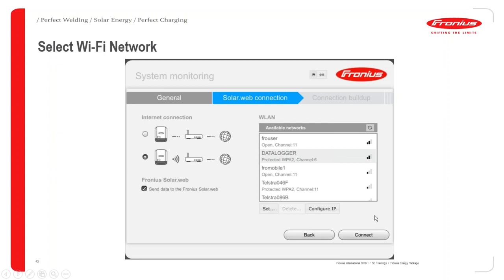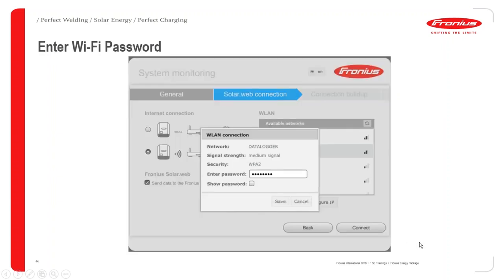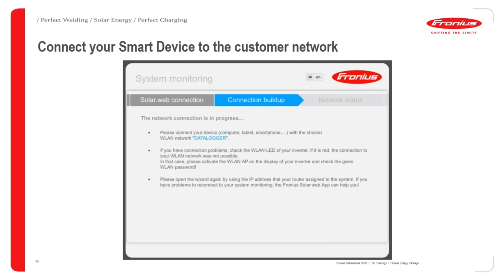Okay, so once you go into the Solarweb wizard, it'll come up with this page again, which you shouldn't need to make any changes on because you did that before. So it's getting confirmation that the general settings are correct, because sometimes people may do this at a later date. Then you've got your Solarweb connection, which comes up with a message saying that the data is encrypted going to our server. However, you need to install the latest firmware and things to make sure that that's all working properly. So once you've done that, then you've got your Solarweb connection.